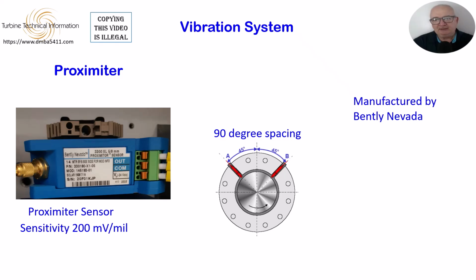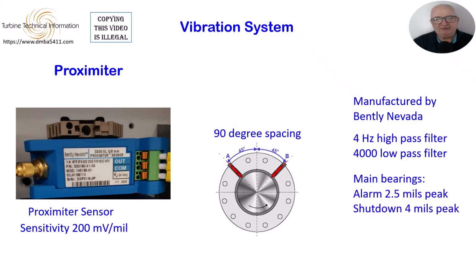Movement of the shaft causes changes in the magnetic interaction between the shaft and probe. The resulting signal returning to the proximeter from the probe will have a waveform that can be processed by the proximeter and then sent to the vibration system for control and display. There is normally a 4 Hz high-pass filter and a 4000 Hz low-pass filter, and the alarms for the main bearings are normally 2.5 mils peak alarm and 4 mils peak shutdown.